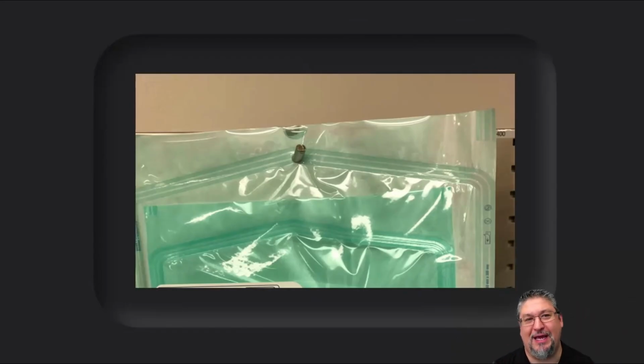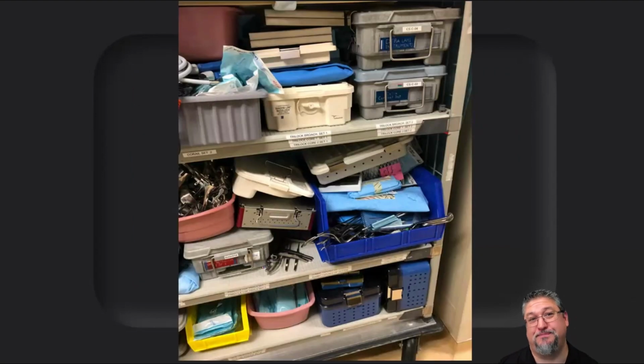But if you vertically hang it, that's not something that the manufacturer has tested. You're putting a lot of weight at the top or bottom of that peel pouch, and maybe it can't handle that in that specific way. They've been validated for a specific setup. Make sure you look at your IFUs and see what the manufacturer recommends before you do anything like vertical hanging. My advice is I wouldn't do it, just because surveyors are seeing it now, and they're looking, first of all, at the holes and seeing what kind of things are being done there, but they're also looking at what the IFU says about peel pouch storage.